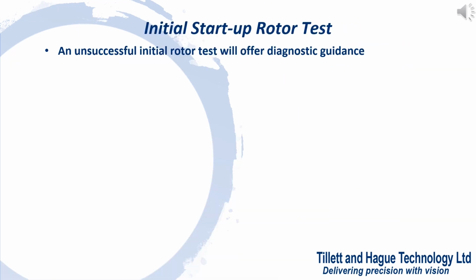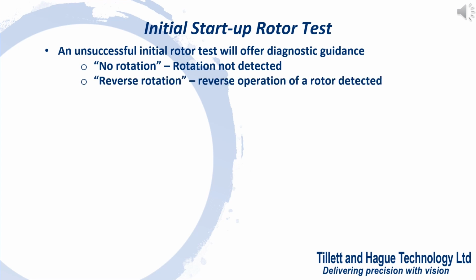If the initial rotor startup test is unsuccessful, messages to help diagnose rotor faults are displayed. They include no rotation, indicating that sensors did not detect rotation, indicating a possible sensor error, or rotor power supply failure. Reverse rotation, suggesting a possible wiring fault, or for hydraulic rotors, the hydraulic supply could be reversed. Comms fail indicates an internal communication fault has been detected. Turn the system off and check connections.